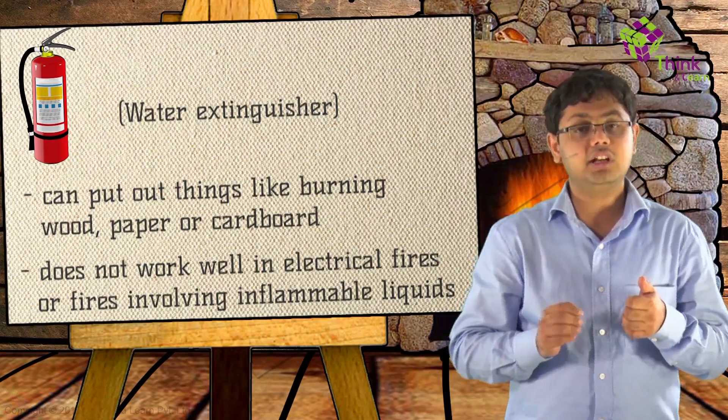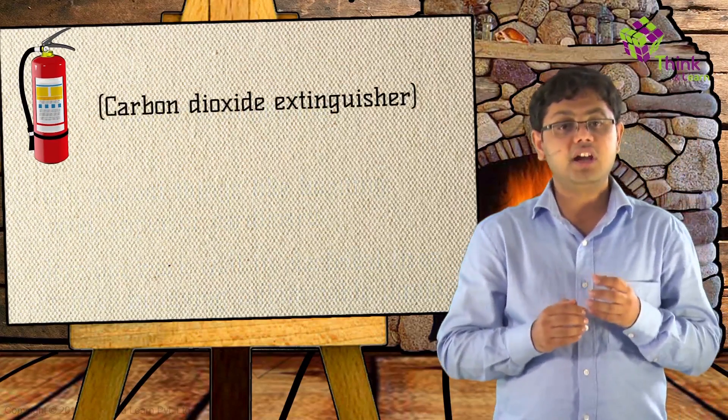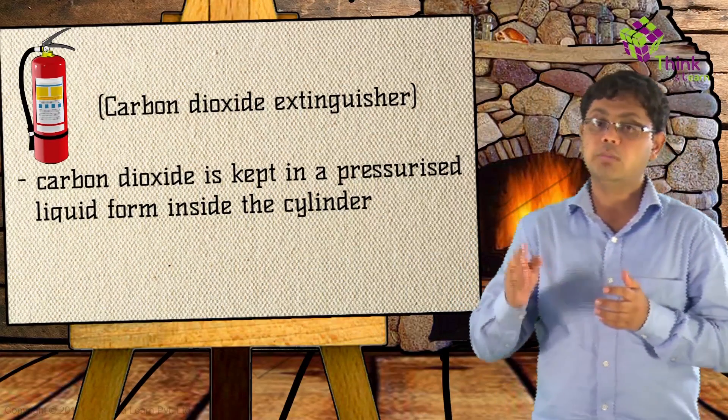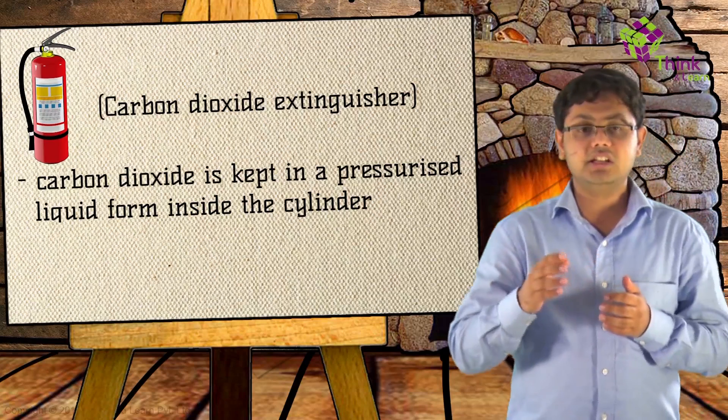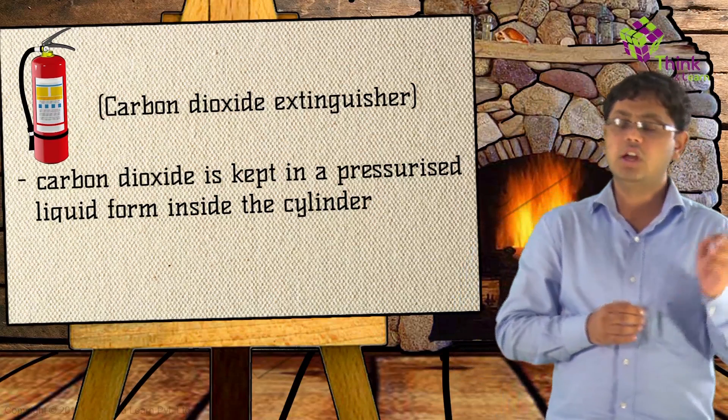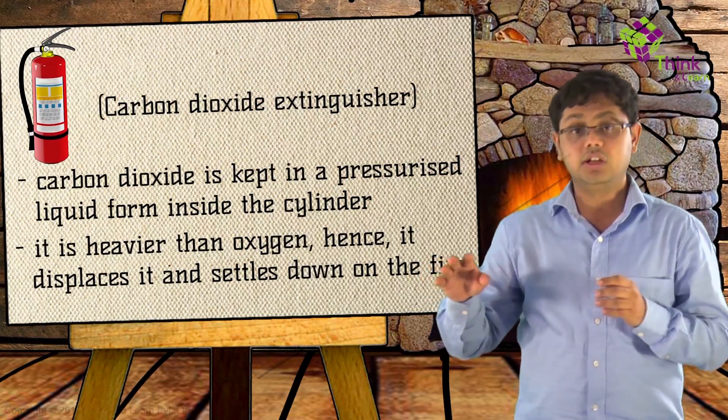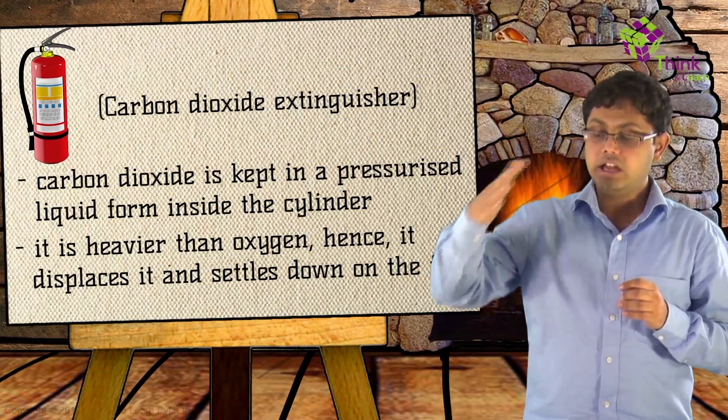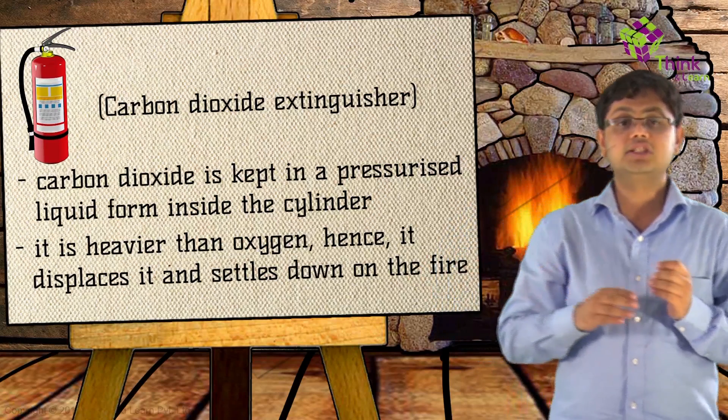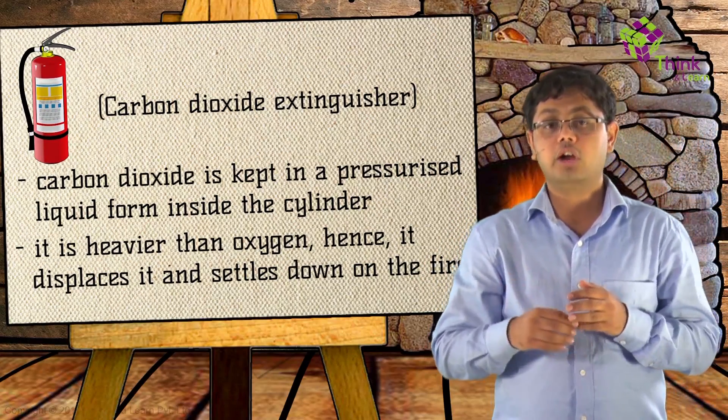One popular fire extinguishing material is pure carbon dioxide. In a carbon dioxide extinguisher, the carbon dioxide is kept in a pressurized liquid form in a cylinder. When the container is opened, the carbon dioxide expands to form a gas in the atmosphere. Carbon dioxide gas is heavier than oxygen, so it displaces the oxygen from the surroundings and it basically settles upon the fire itself. This sort of fire extinguisher is common in restaurants because it won't contaminate the cooking equipment or food.